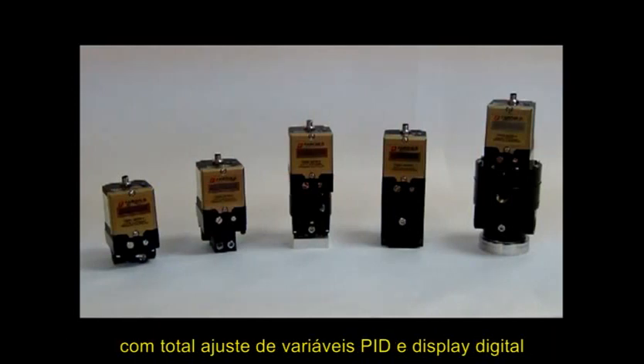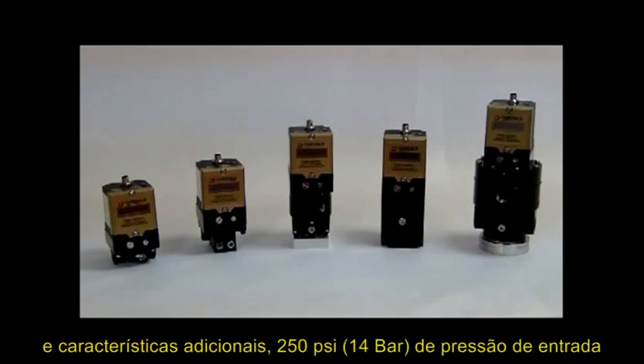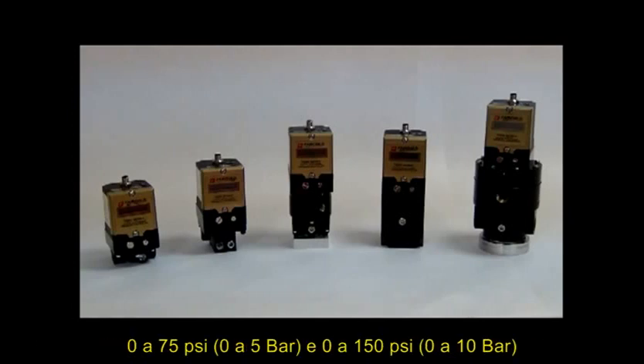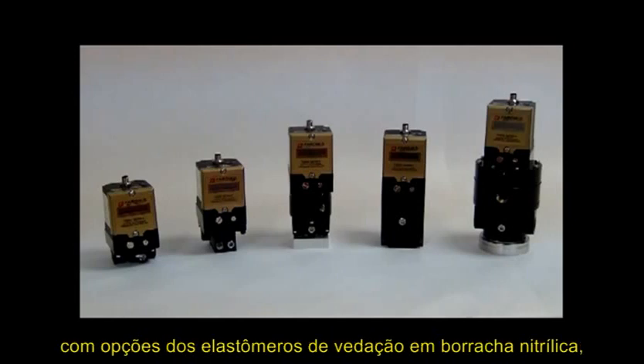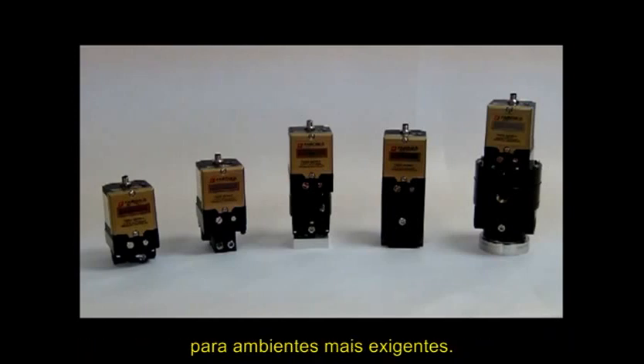Introducing the Fairchild T9000 family of I2P transducers with full PID tuning capability and digital display. Additional features include 250 psi supply pressure capability and three pressure ranges: 0-30, 0-75, and 0-150 psi output, along with elastomer options of nitrile for most applications and Viton available for more demanding environments.